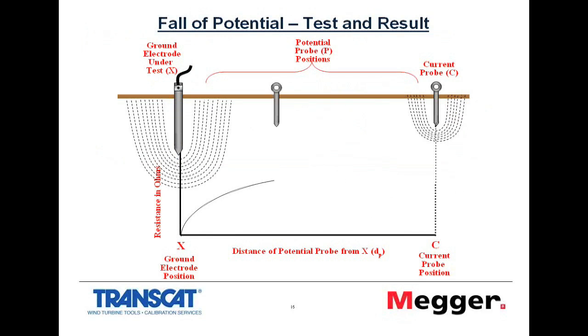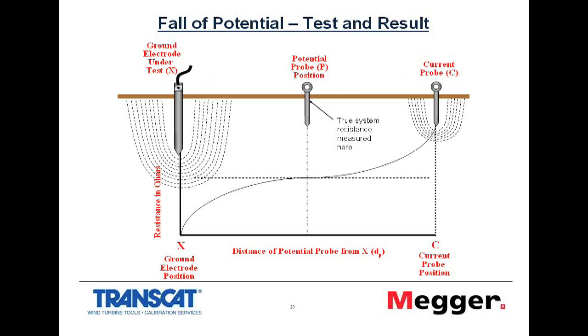As you can see, as I'm moving across, I'm taking the resistance value I measured with the instrument, and I'm plotting it on a graph. Now, when I finish the graph, hopefully it will look a little bit like the graph represented here. It may not be exactly the same shape, but effectively I'm looking for a flat in that graph. The flat area represents the area where I'm outside both spheres of influence. Now typically that appears approximately 62% of the distance between the ground system I'm measuring and the current probe position.